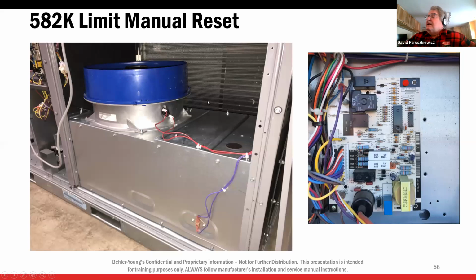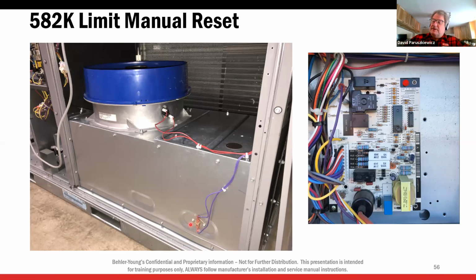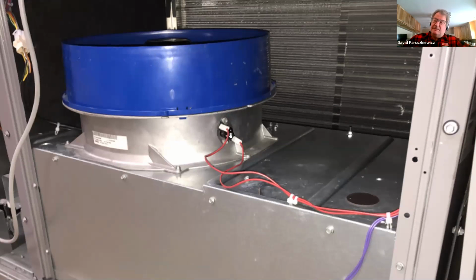So, limit reset. Before we move on, I want to talk about this limit here on the 582. This is a picture of that Axion blower motor that we've talked about. And right here on the side is called the stator limit. Now we have our main limit down here. Let me change back to my laser pointer. Down here with the 2 purple wires, that is our main limit. If that trips, that'll show up here. This limit here, if I zoom in close, you can see it, there's a red reset button on this limit. It's on a unit that's built before the middle of 2020. This is a manual reset limit.